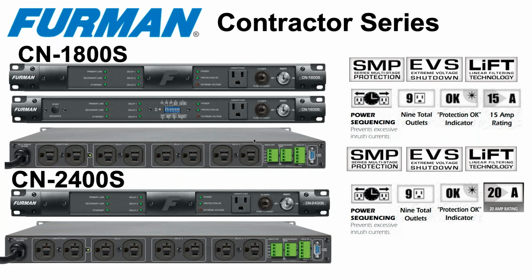Now, with these contractor series units, you can daisy chain up to 50 of them together. There are some dip switches in here for control, for timing and whatnot. The first one in the chain will be primary, and that's dip switch 8. Leave that up. On the rest of them that you're going to utilize, you'll put them in secondary mode. Everybody after the first one is a secondary device. Put dip switch 8 down, and now just use 2 wires.